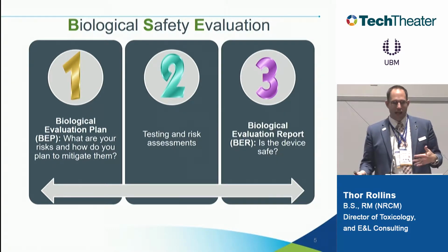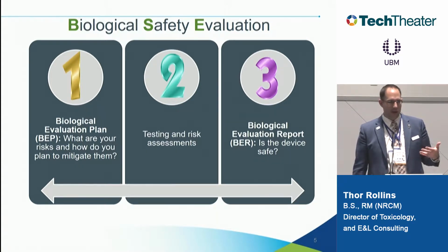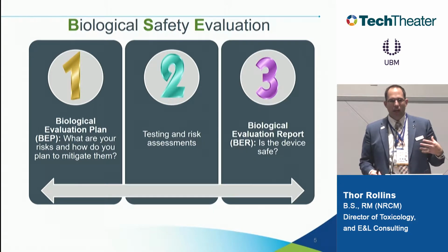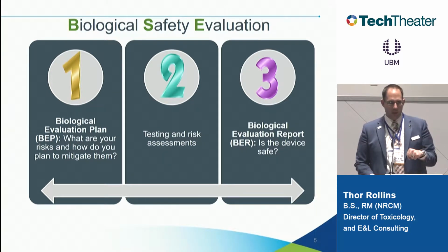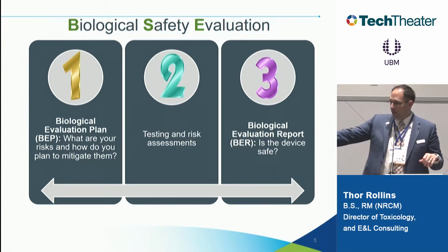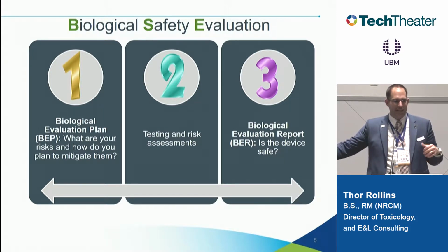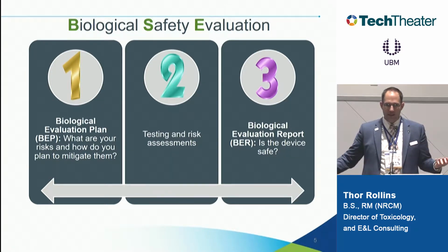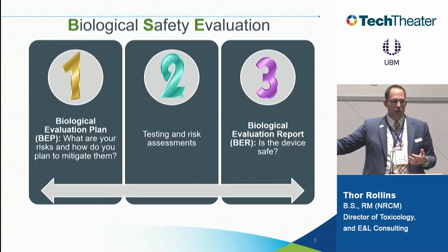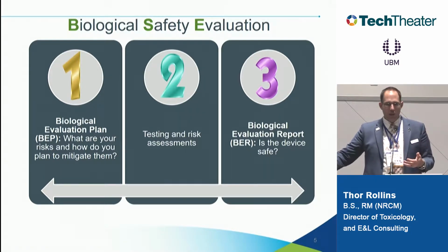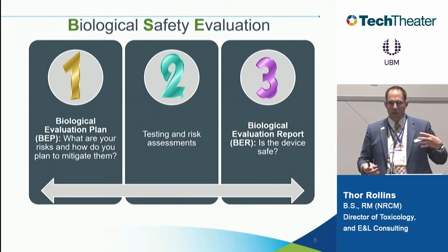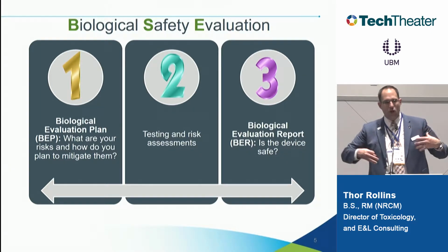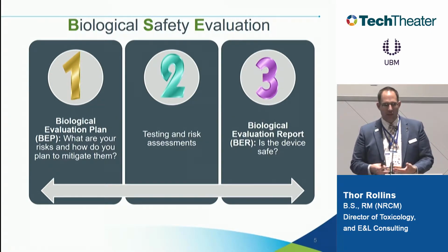So ISO 10993-1 is in public draft, so it's a brand new standard. This new standard is relying more on a risk-based approach for biocompatibility. So this type of work is what is needed going forward for all devices, which is you need to do an initial risk assessment, including a biological evaluation plan. So that risk assessment talks about what's the risk of your device and how you're going to mitigate those risks by either testing or some kind of assessment.